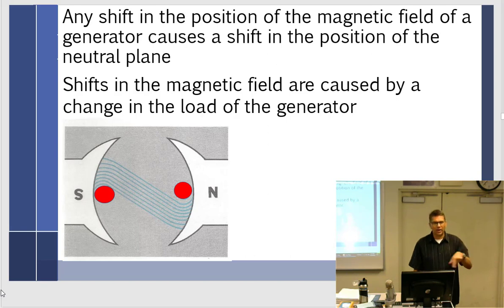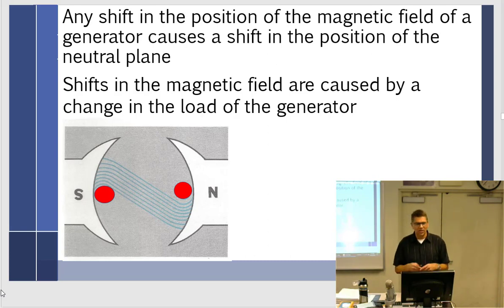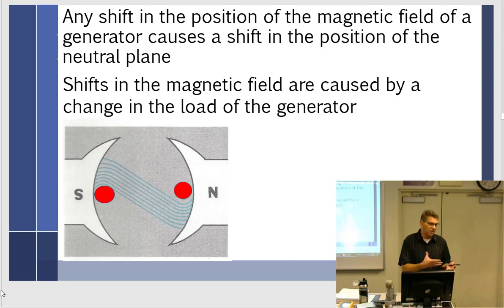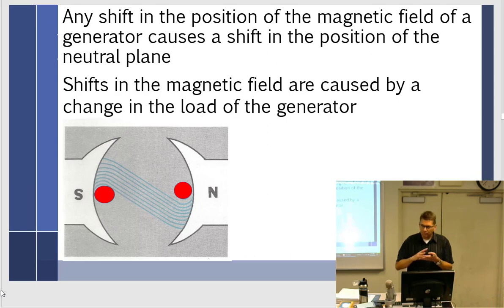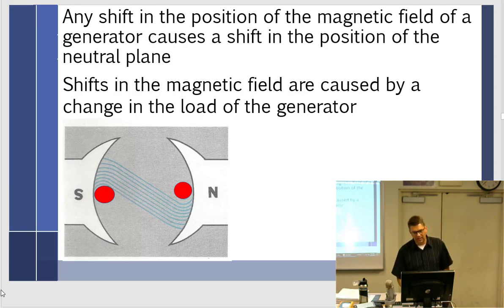That current flows through the loops of wire, creating more of a magnetic field, causing more distortion. That's what it means: caused by a change in the load. If I had no load, there would be no current flow and the neutral plane would go back to where it was. The neutral plane shifts with the load because the current flow in the armature increases its magnetic effect.